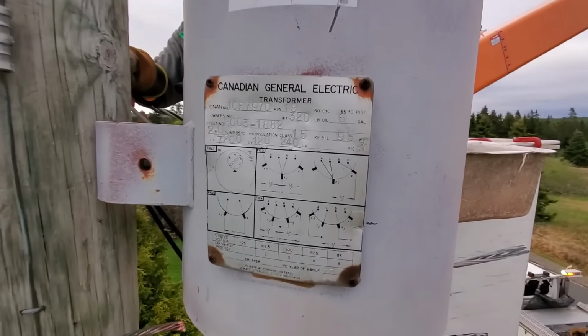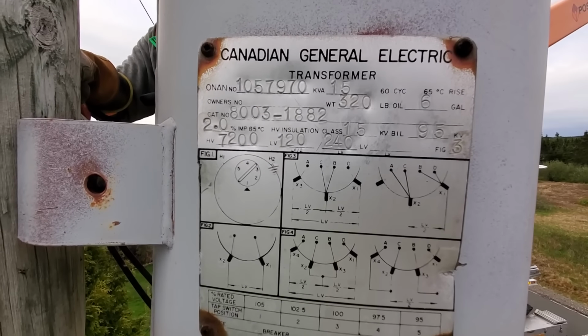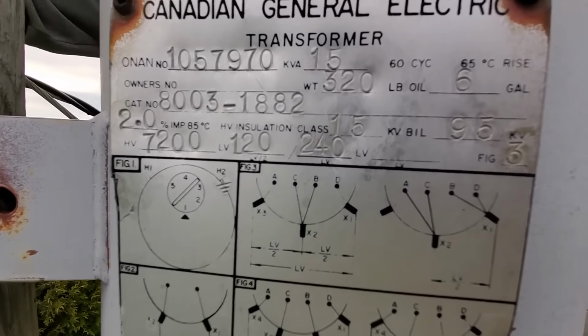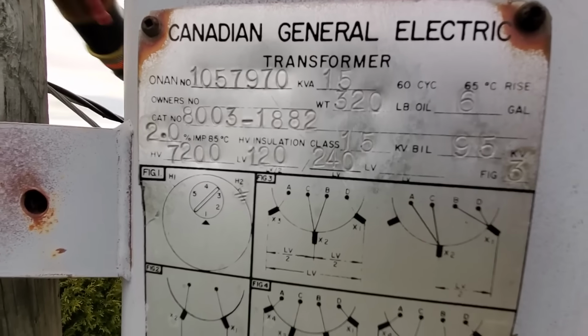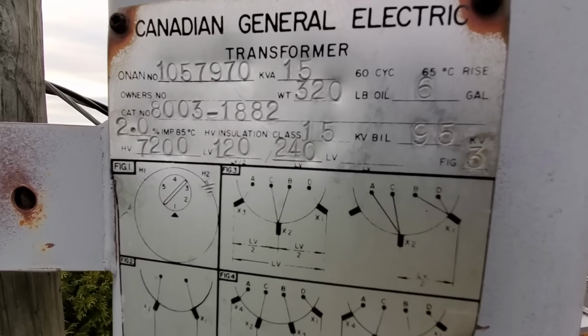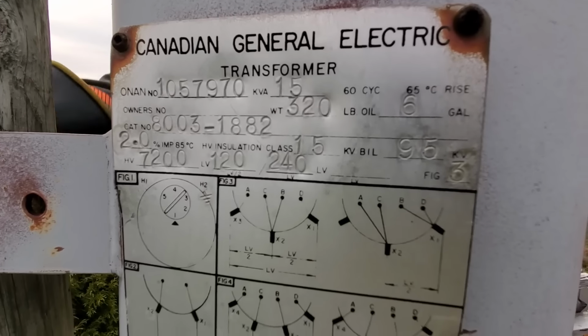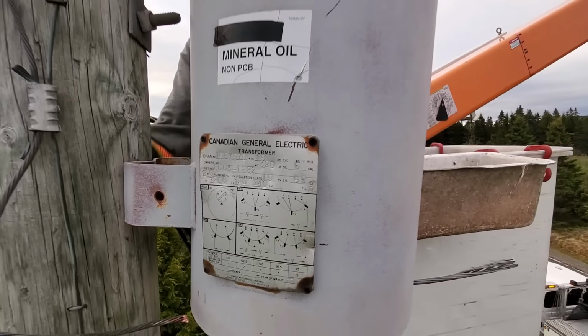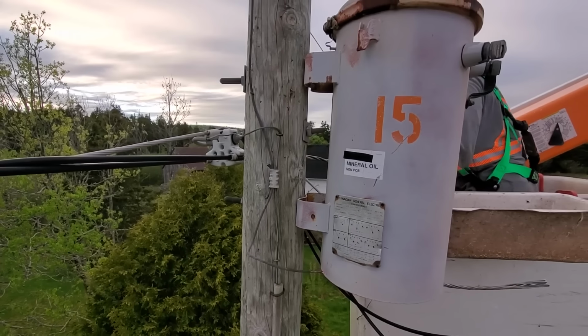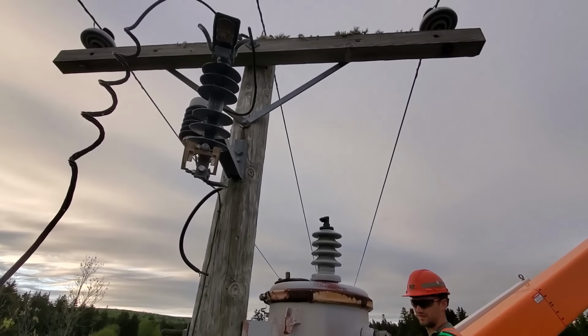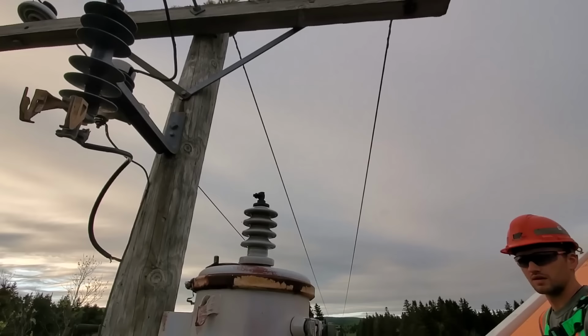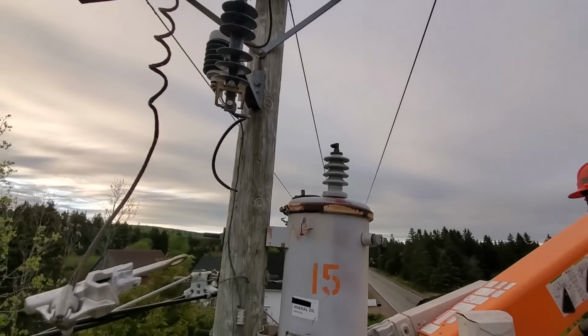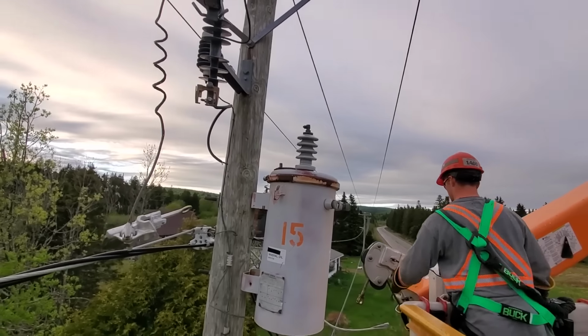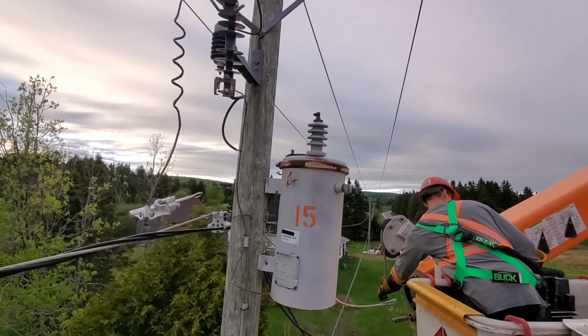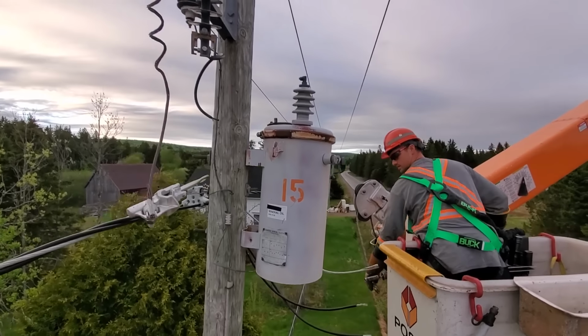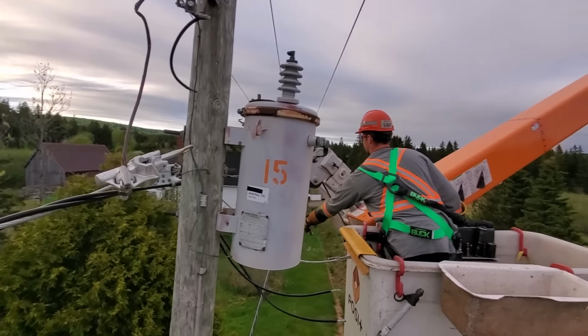So every transformer has a wiring diagram on the side as well. You can see here 15 kVA, 120, 240 volts, 6 gallons of oil, 320 pounds. Ryan's also wearing his class 2 20 kV gloves, where he's got more than his 2'1" clearance, which is what we require. However, some of the tools he's using could breach that 2'1". So that's why he's continuing to wear his class 2 20 kV gloves throughout the work.